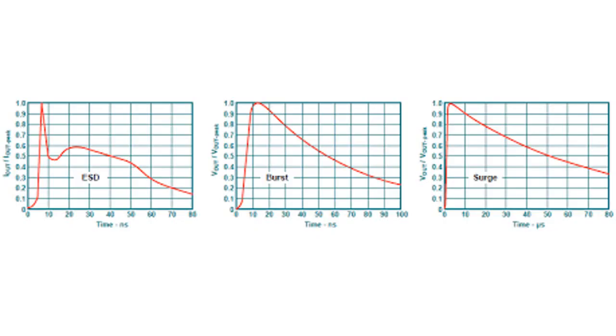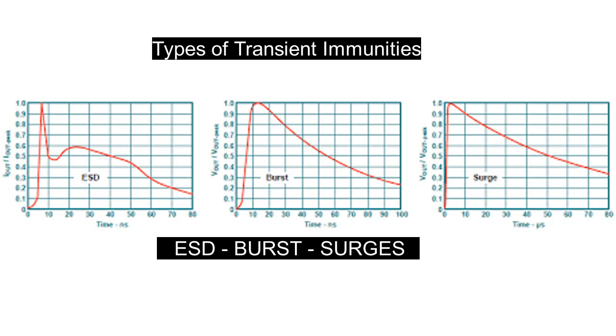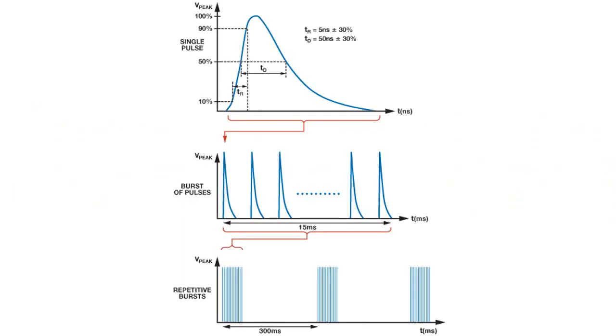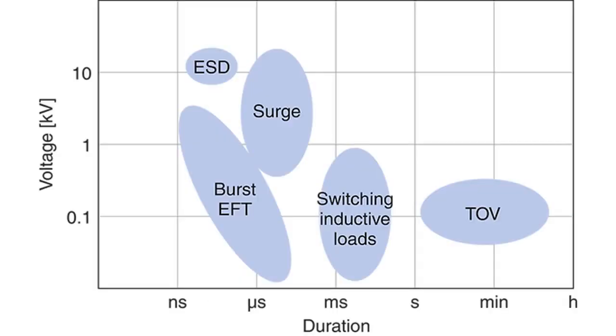Transient immunity: in addition to covering continuous radio frequency phenomena, EMC means ensuring product immunity from several sources of transient phenomena that are present in the electromagnetic environment. Therefore, immunity testing involves applying a repeatable pulse of a defined amplitude and frequency into each relevant cable port in a specified and reproducible manner. These testing can be to ensure immunity to natural phenomena such as electrostatic discharge (ESD) and lightning surge, or man-made such as switching transients and fault surges.